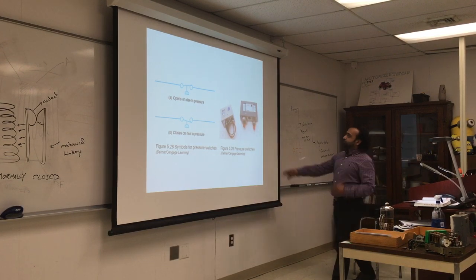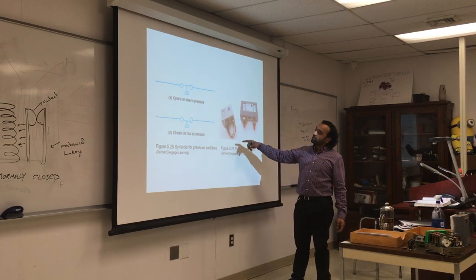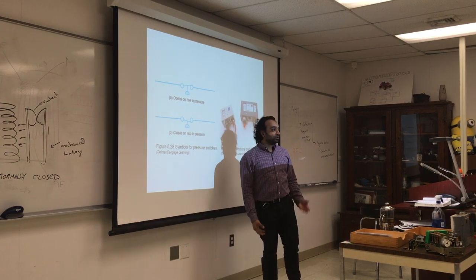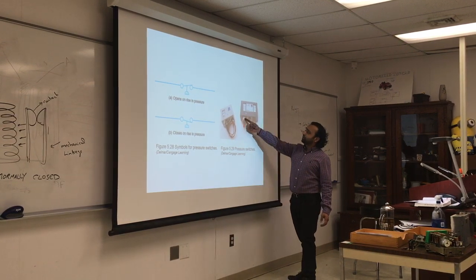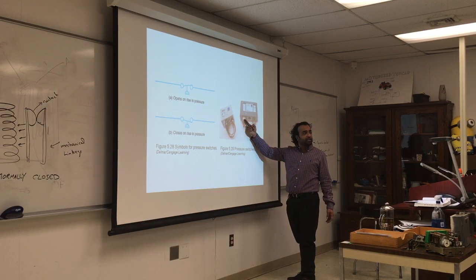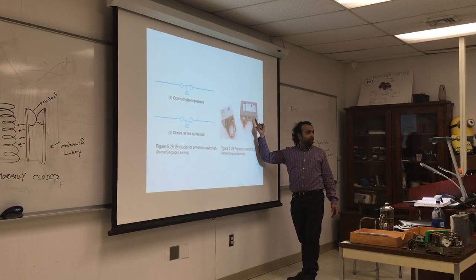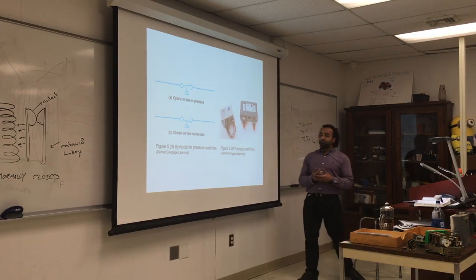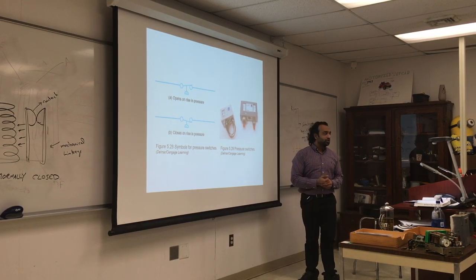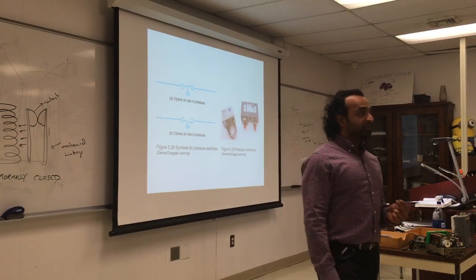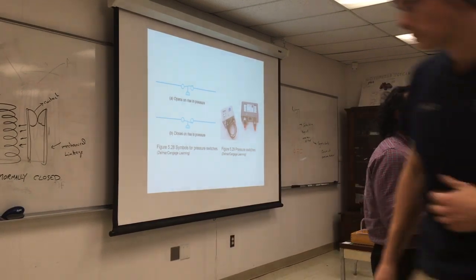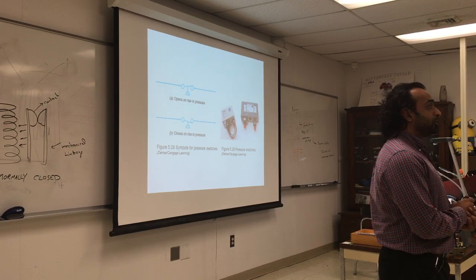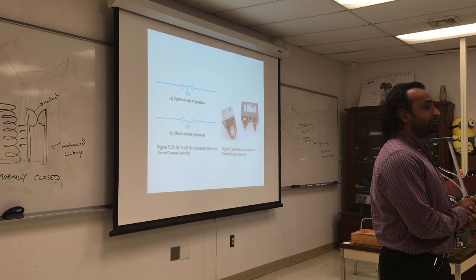Pressure switches, that's what they look like. It's actually newer ones. So basically, they open or close a circuit based on low or high pressure. So this is high and low pressure at the same time, so it maintains the equipment within that set pressure. So either for steam boilers or in a power plant, you're going to have those pressure switches. Also, you will have them in big air conditioner units, like heat pumps. Why? Because we are afraid to exceed the design pressure in that refrigeration cycle, and that will cause us to what? Break the compressor. And that's the most expensive part of your equipment.